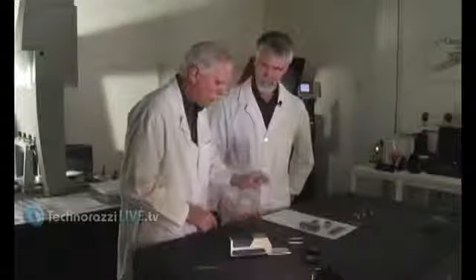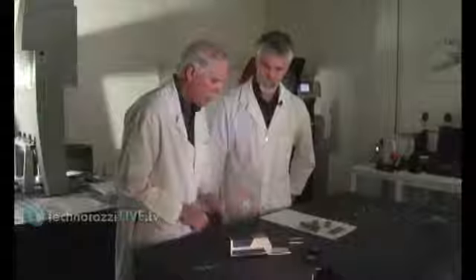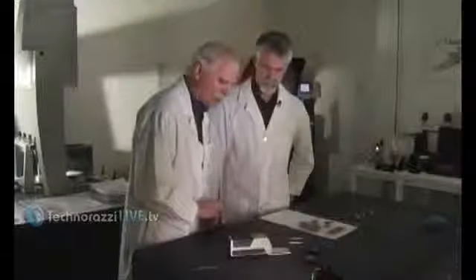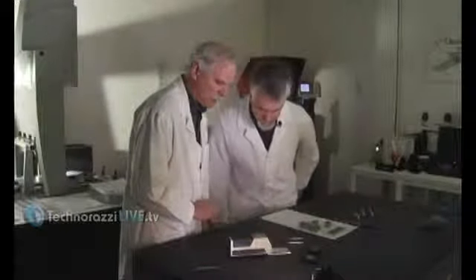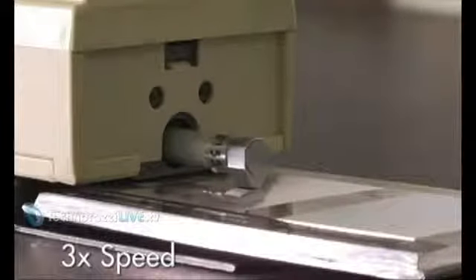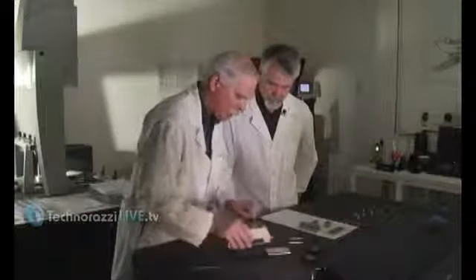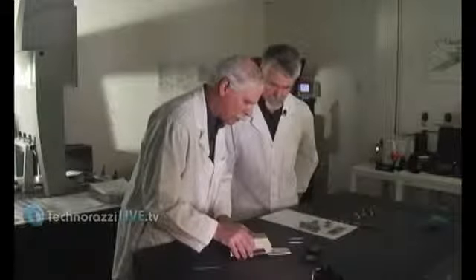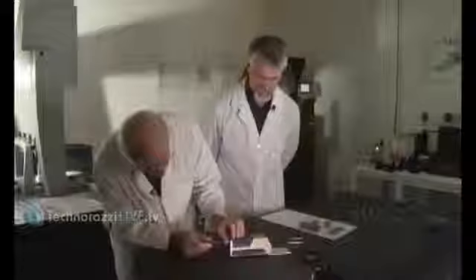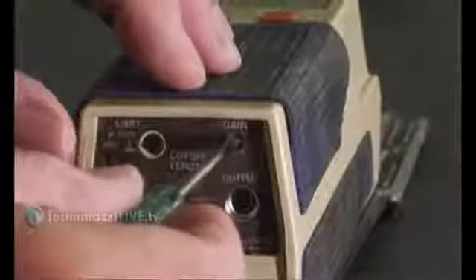What we'll do is press the start button, the stylus will move, and it's taking 5 segments typically for RA. 5 segments, and then it'll average them. So I'll push this, and the stylus just moves very, very slowly across, and it comes out with a number for RA. Now we're set up on a standard. We know this is 116.6 microinch. It showed at 115, so we have to reset the gain a little bit. Okay, now we're going to turn the gain screw a little bit higher because it's reading low.